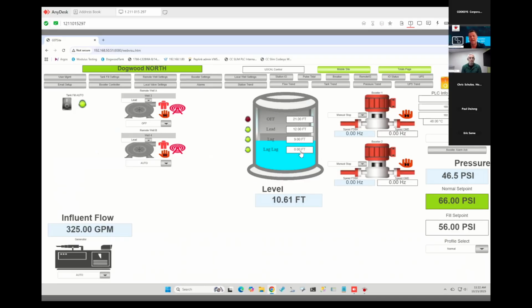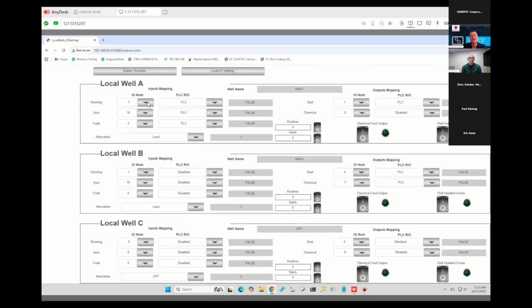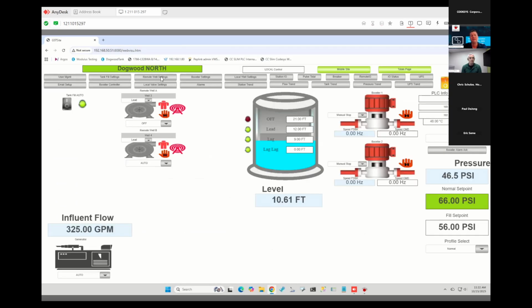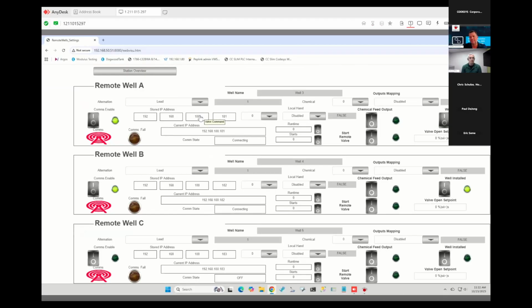So here's my tank. I've got my on and off fill. I can go to my local well settings. I've got all my IO to map. I can go through the PLC right on board, remote IO, or if I want remote wells, here we are with our Modbus TCP connections. So from here, I can actually put in my Modbus TCP address and enable my comms to start and stop wells over Modbus. And in some of these systems, everything's configurable here.